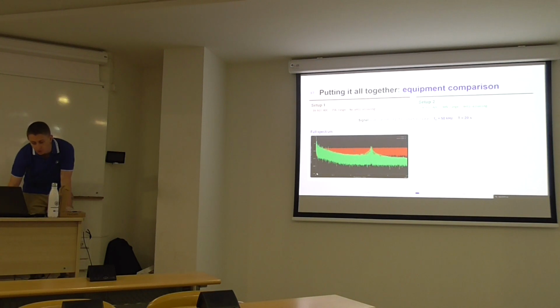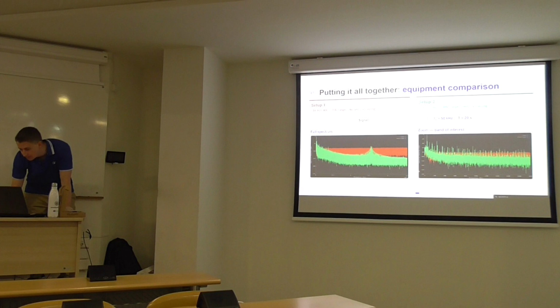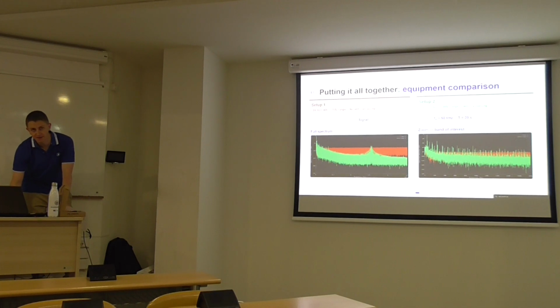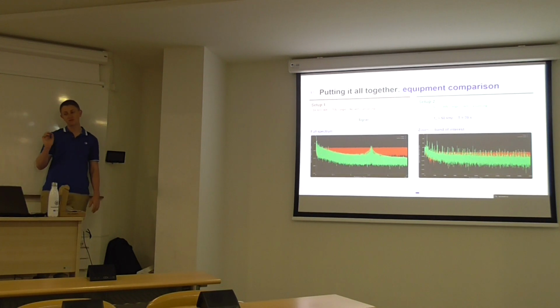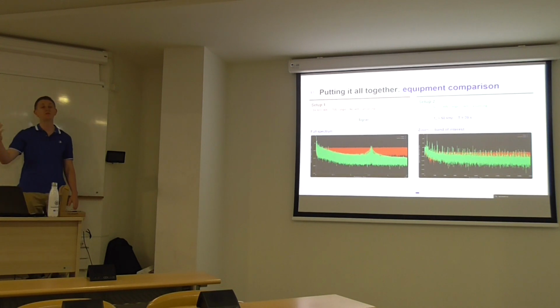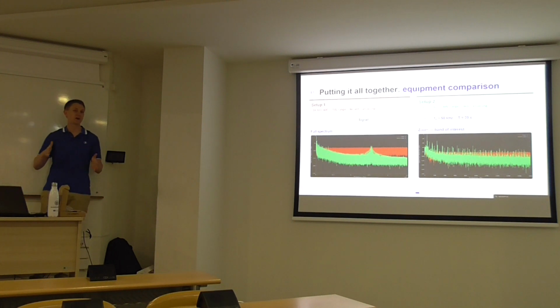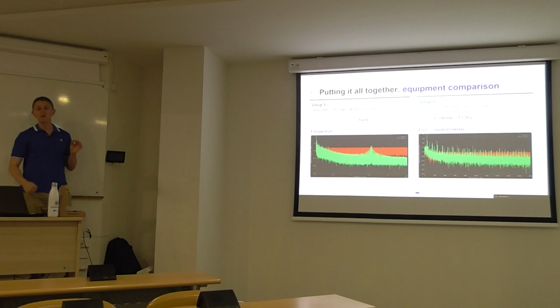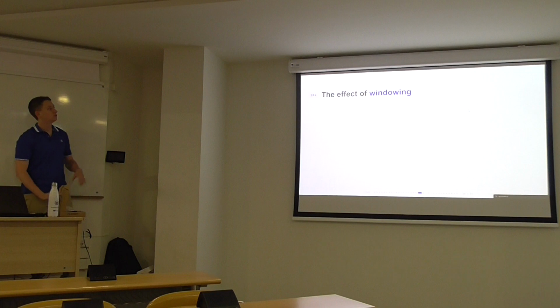Now let's zoom from 0 to 2 kHz more or less, and see how there are a lot of harmonics here that can be seen in the green spectrum but that are below the noise floor in the red one. So the difference is that setup 2 has more bits, and we have used an anti-aliasing filter. Okay? So it is super important to keep always in mind that the higher the number of bits, the better. Of course, the equipment will be more expensive, but you need to arrive at a compromise. I always recommend a minimum of 12 for sure, and if you can, go to 16. If you can afford it, go to 24.